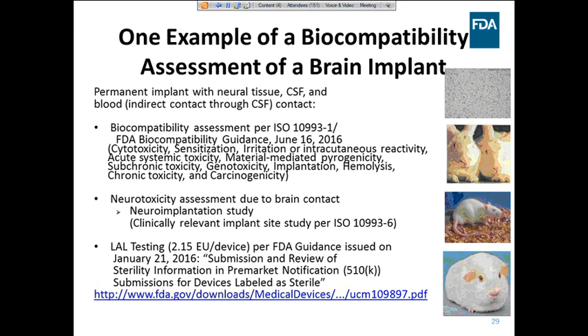In addition to these general biocompatibility endpoints, a neuroimplantation study may also be considered to assess the neurotoxicity due to brain contact. Also, as I mentioned earlier, the endotoxin limit should not go over 2.15 endotoxin units per device for this type of device.